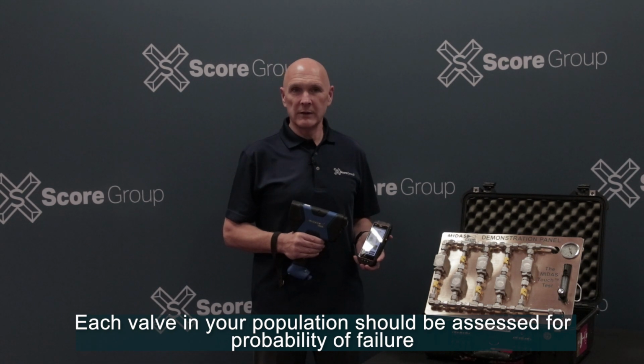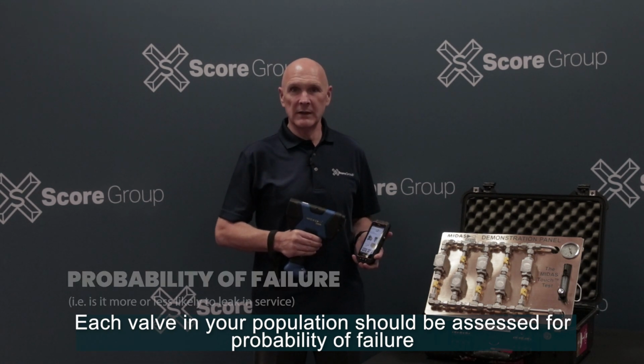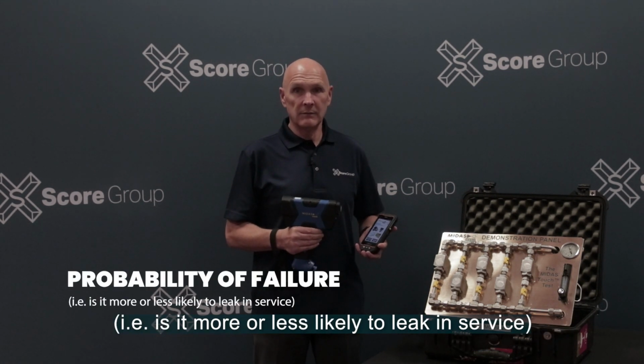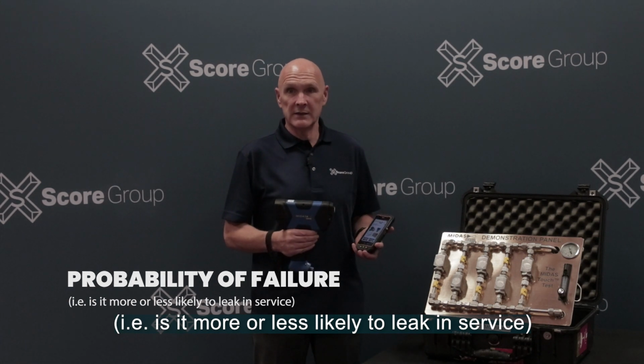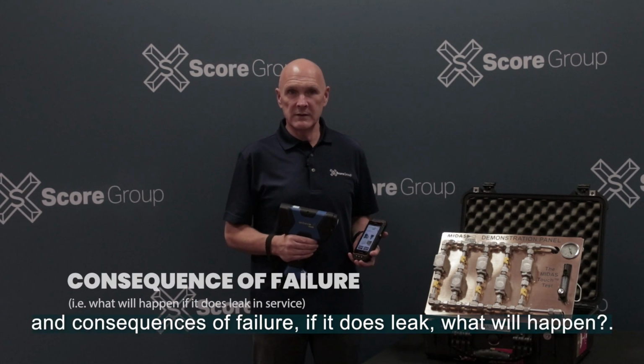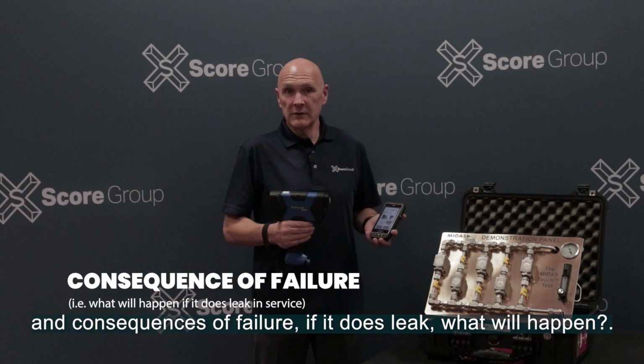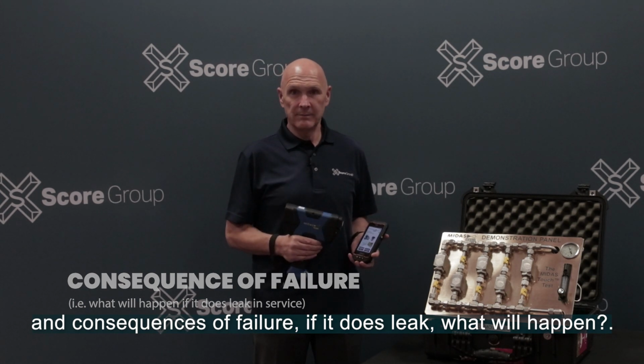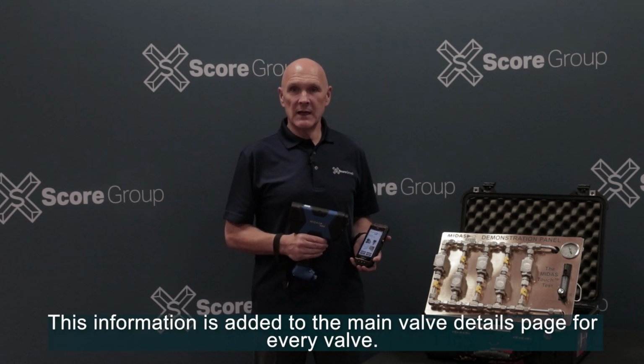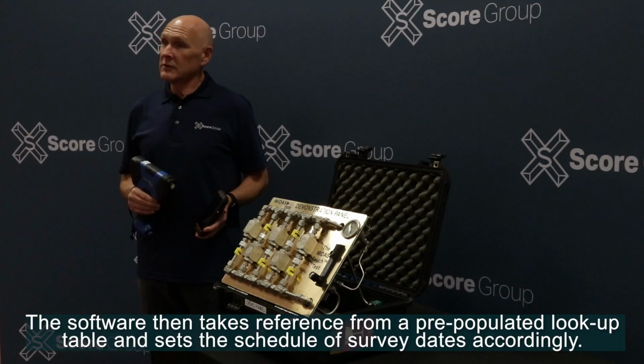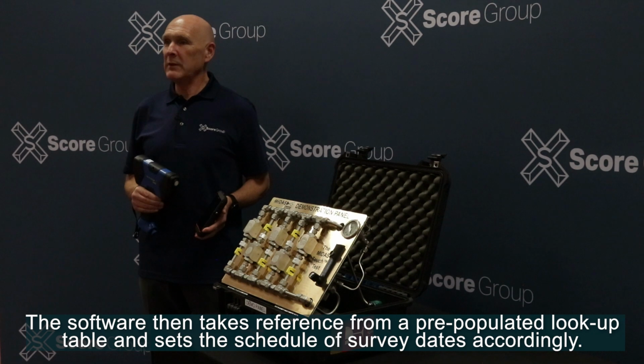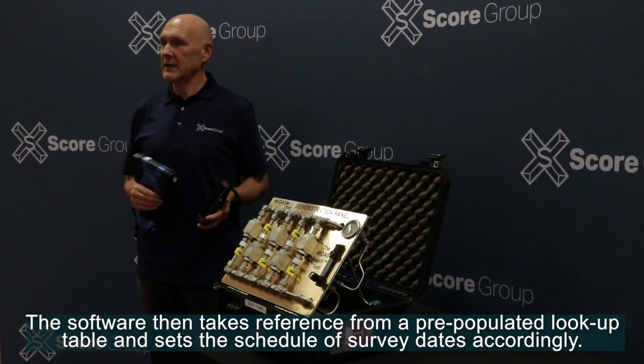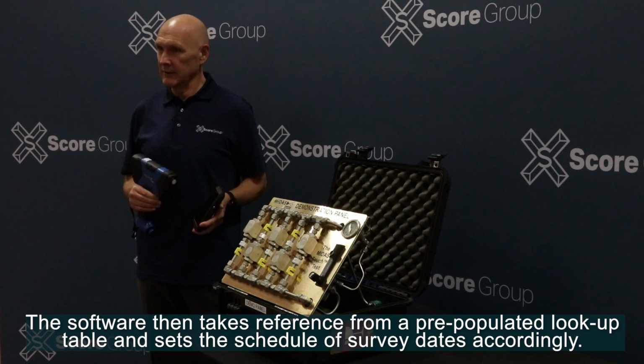Each valve in your population should be assessed for probability of failure, i.e., is it more or less likely to leak in service, and consequences of failure. If it does leak, what will happen? This information is added to the main valve details page for every valve. The software then takes reference from a pre-populated lookup table and sets the schedule of survey dates accordingly.